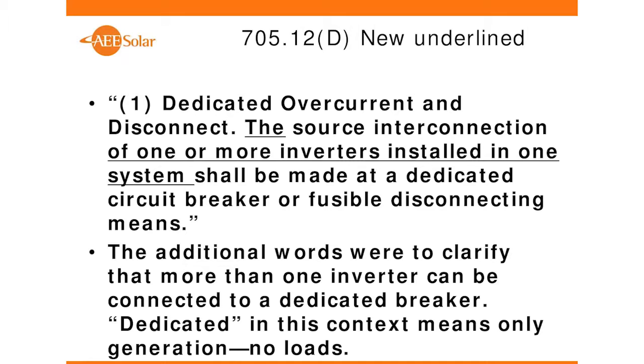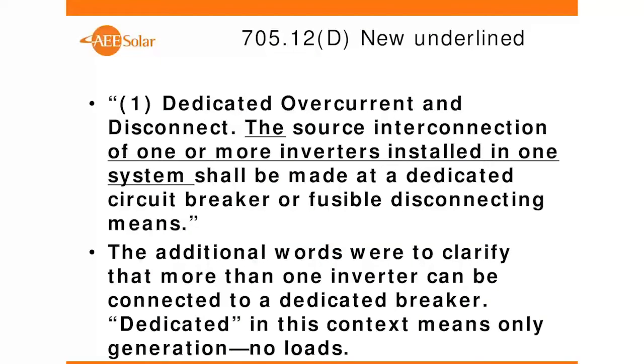So the first one, basically, 705.12(D) has 1 through 6. And it's pretty lengthy. And number 1 on this list of what it has to comply with is going to a dedicated overcurrent protection, or overcurrent and disconnect. And the way it was written, and I hadn't really seen too many inspectors mess this up yet, but I saw it coming, is that it said the source connection shall be made at a dedicated circuit breaker or fusible disconnecting means, which is true, but I could see somebody saying, well, that Enphase inverter you're talking about, that's really the connection for that, you can't connect it to a bunch of other microinverters. You have to bring it back to a circuit breaker every single time.